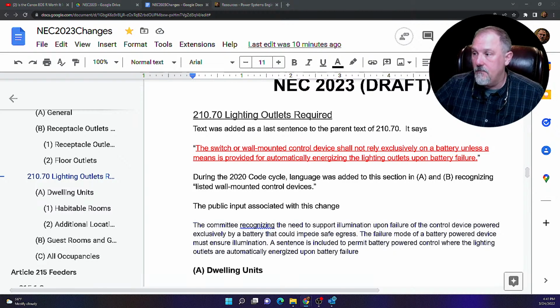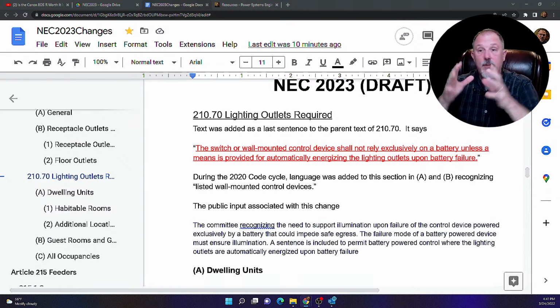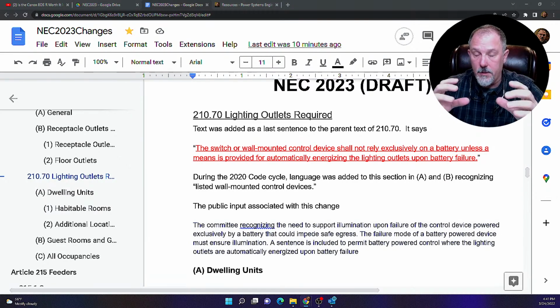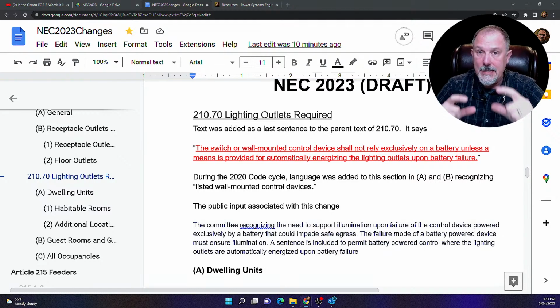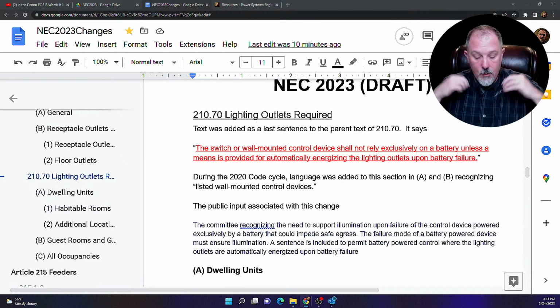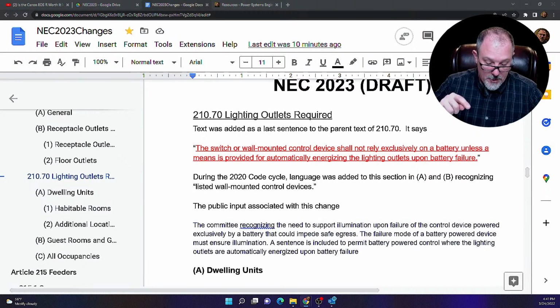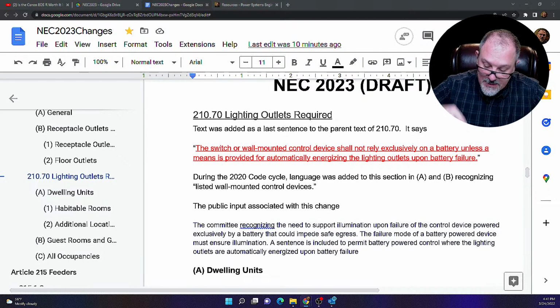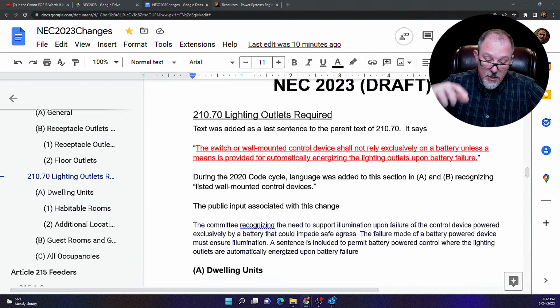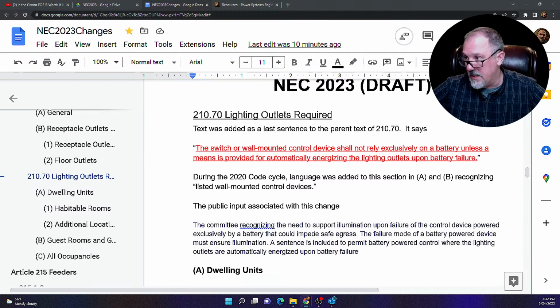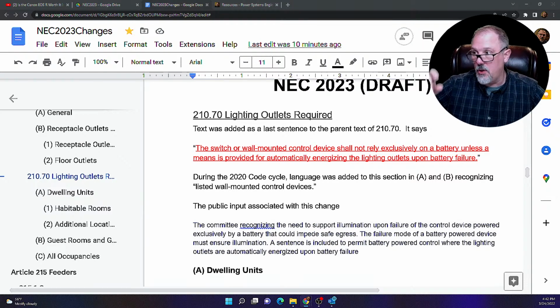So in any case, that's the 210.70 - that was in the parent text. Why is it important to put this in parent text? Because we use that language in A, dwelling units, B, guest rooms or guest suites, and C, all occupancies. We use that generic language of listed wall-mounted control device in all of those, so we had to put something in the parent text of 210.70.